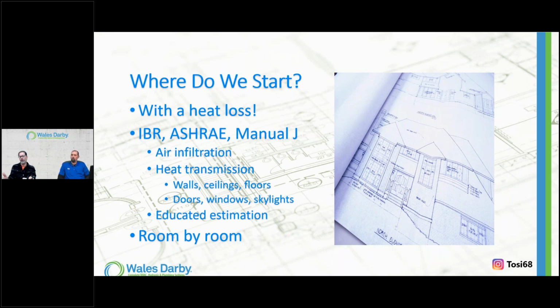So basically what I want is somehow to understand, living in your own home, I have no clue if my source makes sense for the load, or my emitters make sense for the load, right? So you can do a quick calc and go around the room and measure all your baseboard, and if it's standard, let's call it slant fin 30, we can figure out an output of BTUs per foot, and then go back to the boiler, like, wow, I have 3 times the amount of emitter BTU output versus my boiler, which could happen.